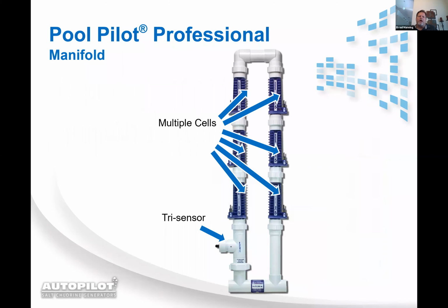This is our patented manifold, up to 6 cells in it. You'll notice that we did move the tri-sensor down here. In a regular manifold, the tri-sensor is up here, but with manufacturing chlorine through these three cells, the last thing you want it to do is hit our tri-sensor. It'll eat away the flow paddle. So the tri-sensor has been moved down here.